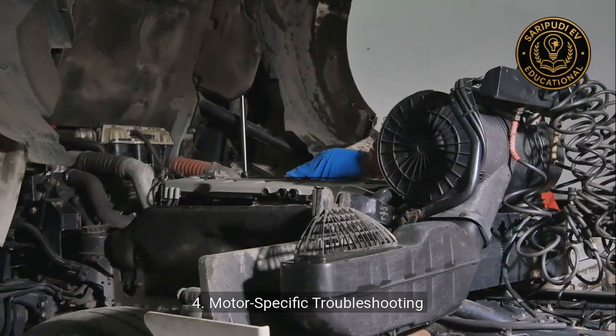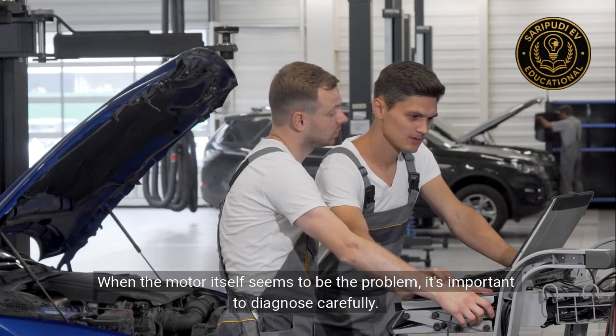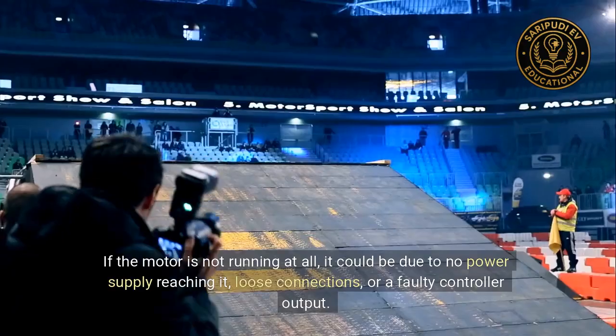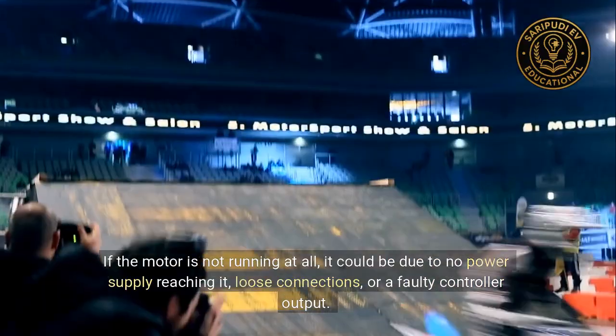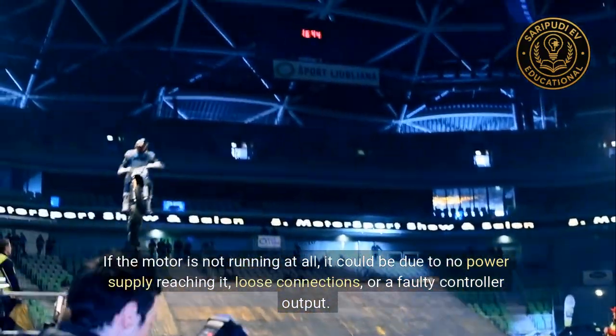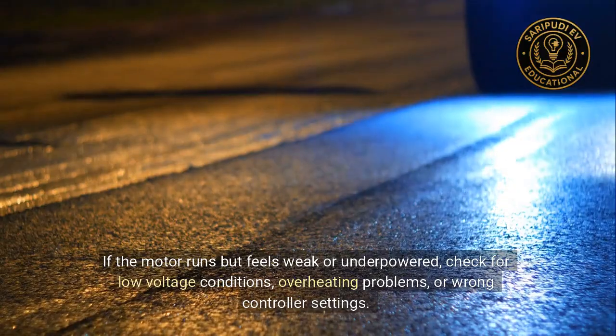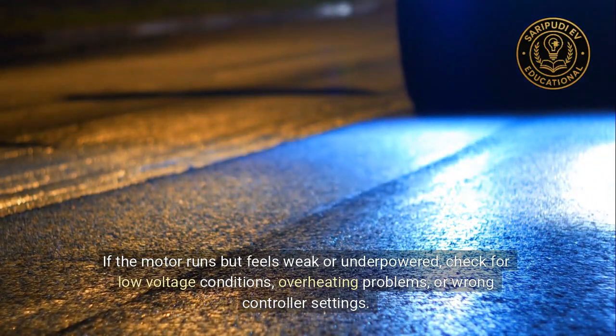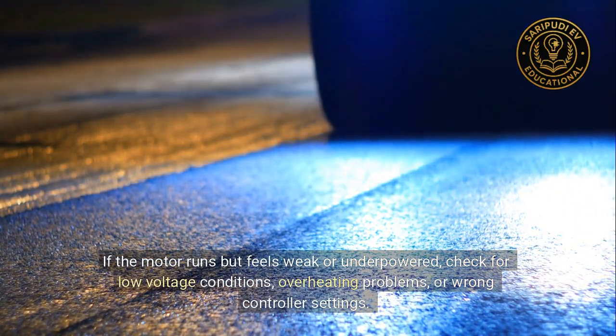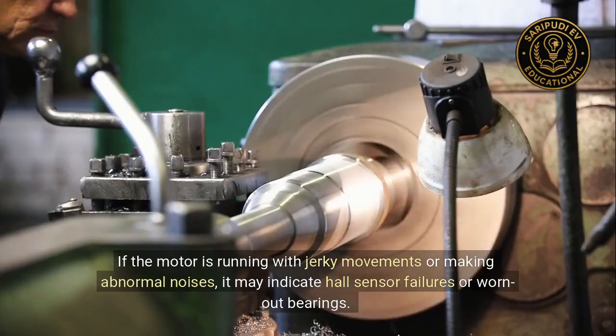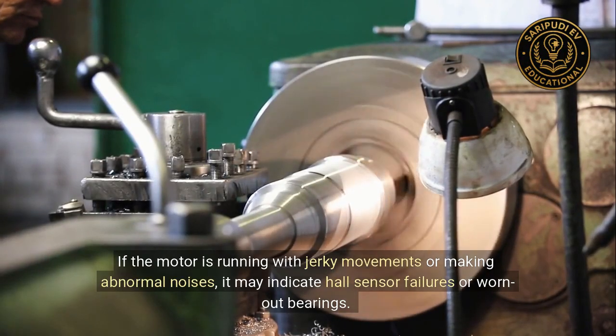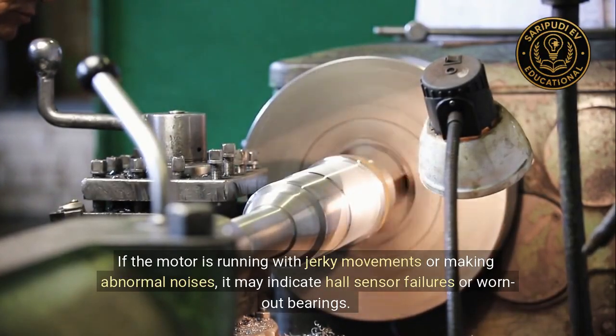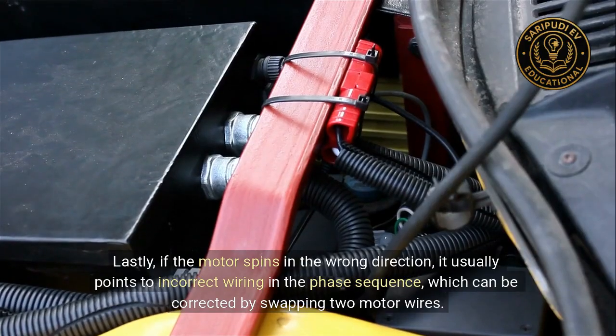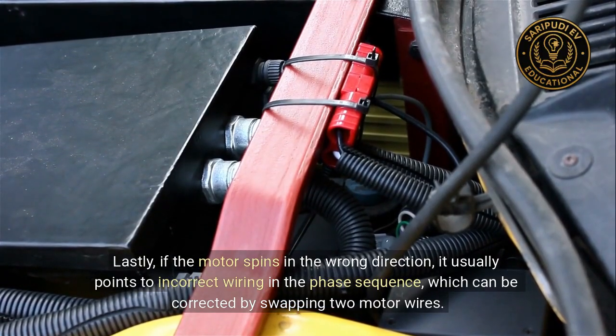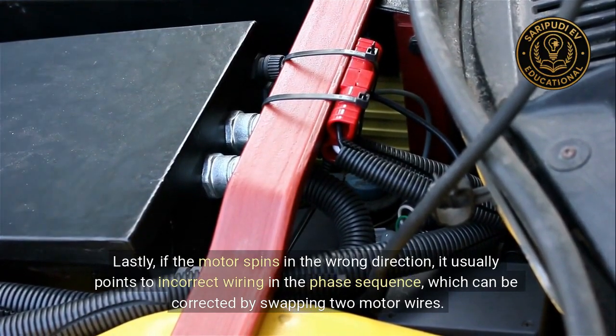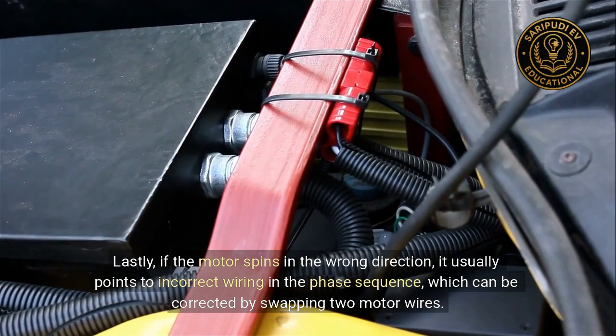4. Motor-specific troubleshooting. When the motor itself seems to be the problem, it's important to diagnose carefully. If the motor is not running at all, it could be due to no power supply reaching it, loose connections, or a faulty controller output. If the motor runs but feels weak or underpowered, check for low voltage conditions, overheating problems, or wrong controller settings. If the motor is running with jerky movements or making abnormal noises, it may indicate Hall sensor failures or worn-out bearings. Lastly, if the motor spins in the wrong direction, it usually points to incorrect wiring in the phase sequence, which can be corrected by swapping 2 motor wires.